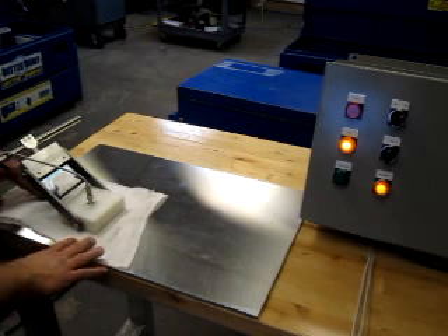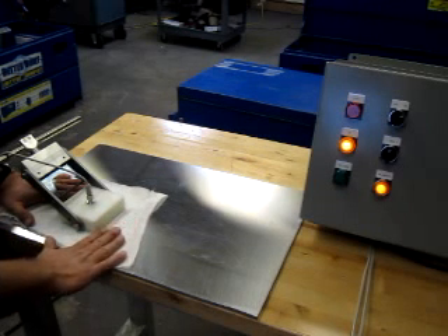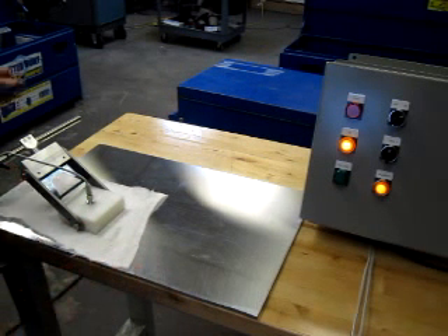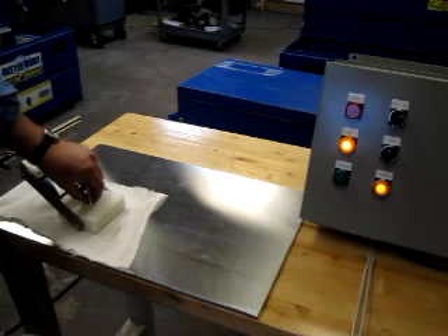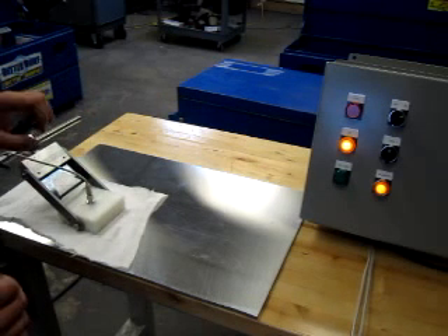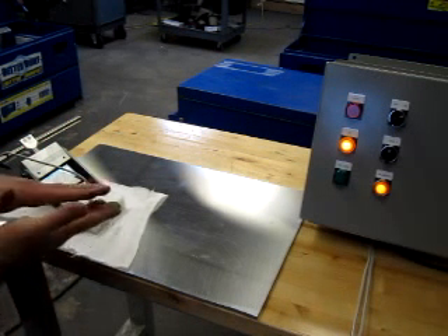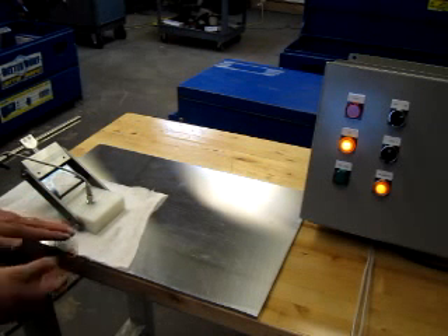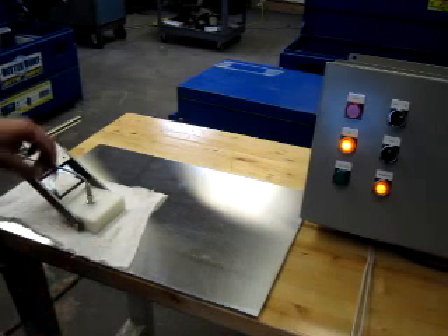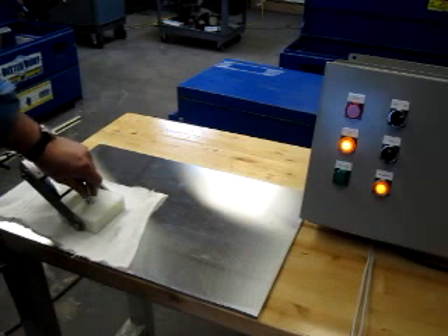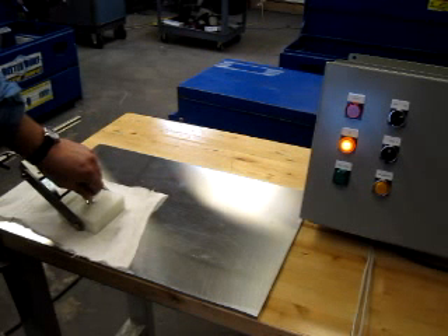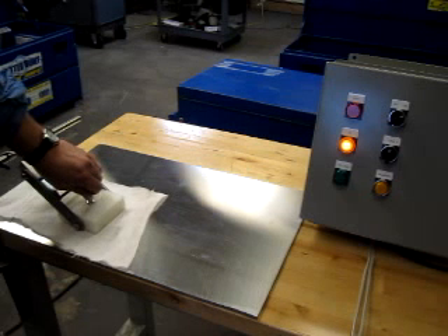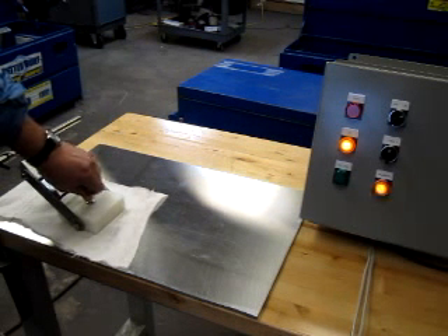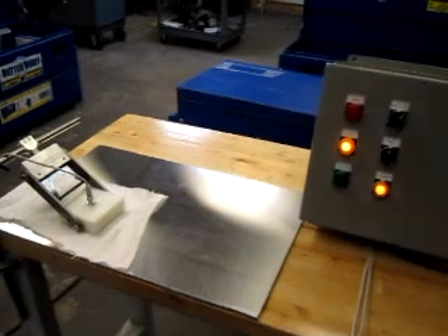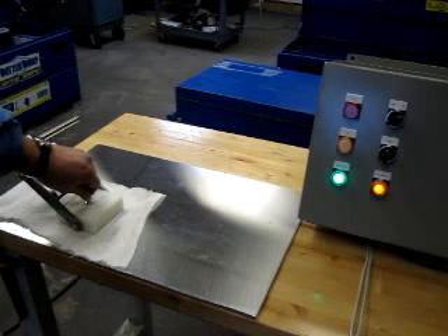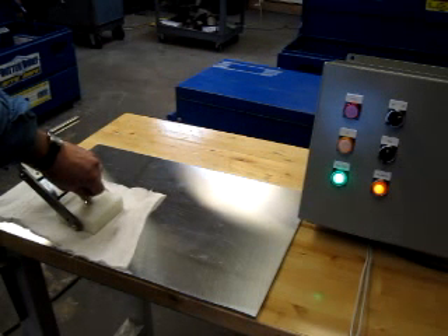The first thing you need to do, of course, is get your material, whatever material you're using, set up, sandwiched in between the shoe and the machine. The next thing you need to do is make sure that this sensor is in the middle of its sensing range, with the material sandwiched in between. So we'll look at the light that's on the calibrate, and if I bring the sensor further away, the light goes out. Bring it in, it comes on. Go in too far, it goes out again. So we're looking for that sweet spot where the calibrate light is on. Once you make this adjustment to get your calibrate light to turn on, that's the first step in the process.